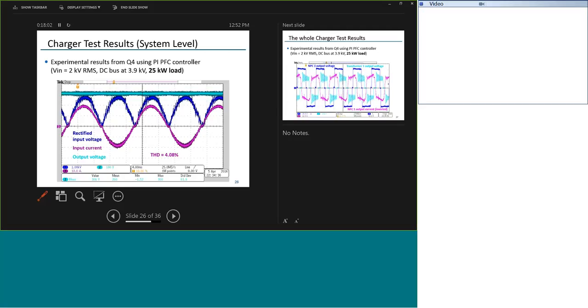You can see the THD is 4%, a little higher than we wanted, and that's due to this issue or distortion close to zero crossing. That's due to the use of the PI controller that wasn't optimized.